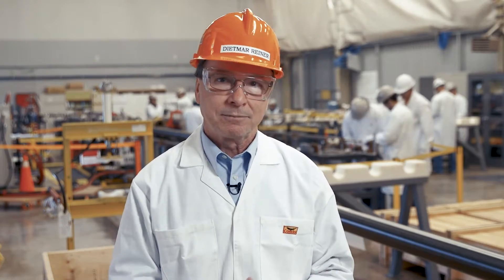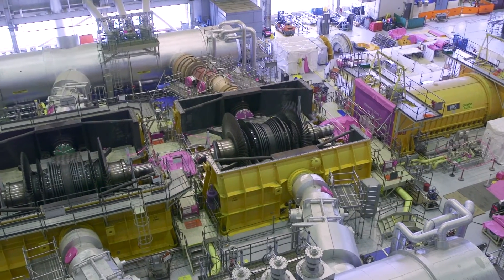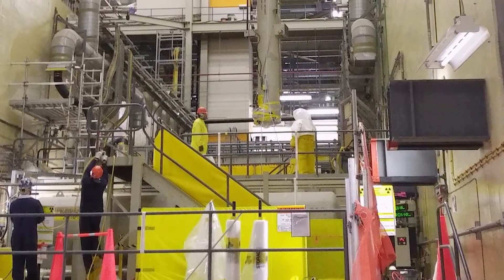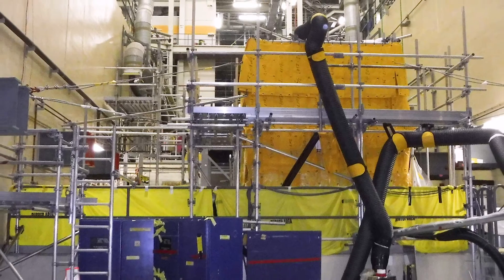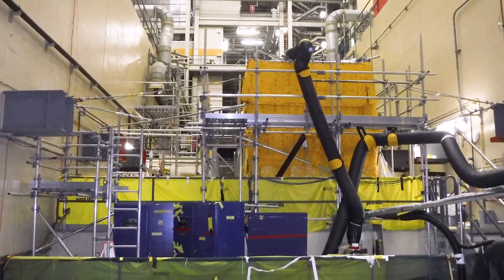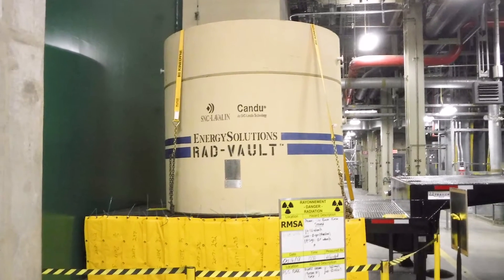The big news is our success with bulk work. This includes balance-of-plant projects like our turbine and generator overhaul, as well as reactor safety systems, which are all now complete. This work also involved the cleaning of our boilers, where over 10,000 pounds of magnetite was removed. The boilers are in excellent condition and will safely run for decades to come.